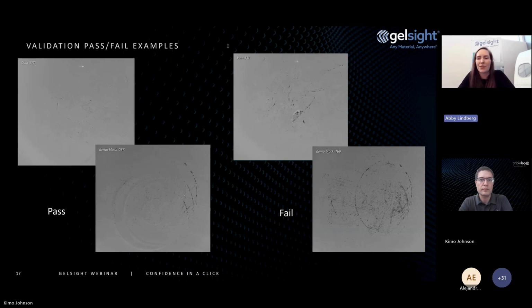We also do have a lot of customers that have a requirement that they check that their system is reporting within a spec. And a lot of times that check can't use the same target that you're using in the calibration process. So we can't validate on the same reference that we've calibrated with. So really the validation plate is optional. It can be purchased as an add-on for your system, but it really can help you make data-driven decisions about gel replacement. So with that, I think we'll wrap up here and see if there are any questions in the Q&A.